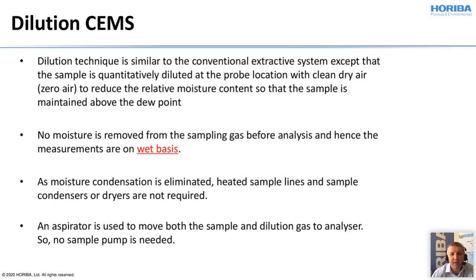The last one is the dilution CEMS, where we have the dilution technique similar to the conventional extractive system, except that the sample is quantitatively diluted already at the probe location. With clean dry air, which is zero air, similar to the permeation air, the relative moisture content will be reduced in such a way that the sample is maintained above the dew point. So, similar to the permeation dryer, we can take the unheated line from the probe to the cabinet with the analyzer installed.